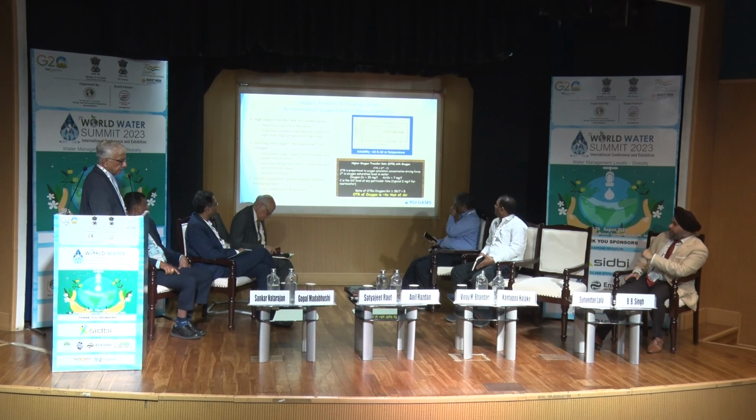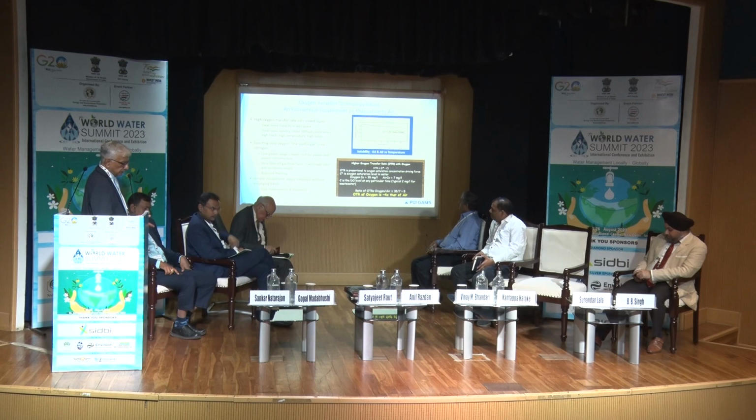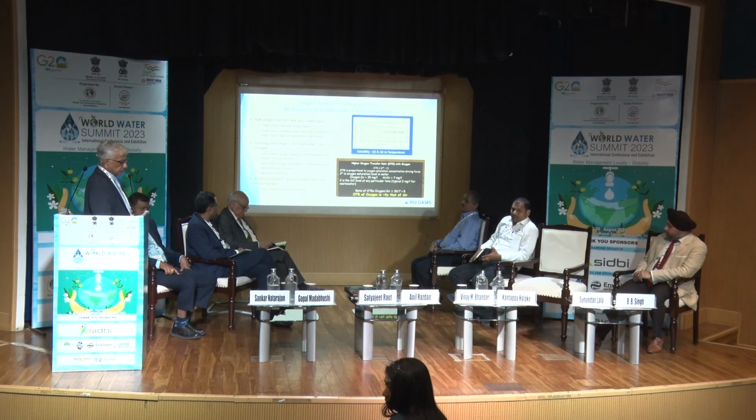And these are the driving forces which allow you to keep more biomass in the tank, or reduce the aeration tank capacity by 50%, or get a throughput increase of the effluent flow from 60 to even 100%. So these are some of the benefits due to these properties. And I'm going to tell you how we dissolve the oxygen into the wastewater.